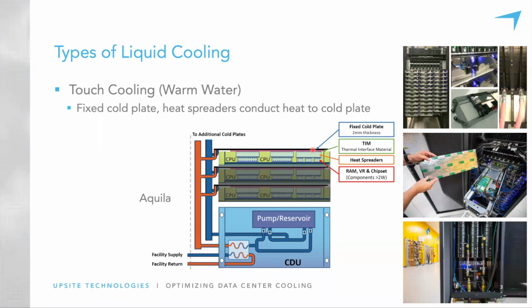Now, like the other touch cooling, there's a cooling distribution unit down at the bottom of the cabinet or in the row, a row mounted cooling distribution unit, which is another liquid to liquid heat exchanger for passing the heat to the facility liquid that will remove the heat from the building.